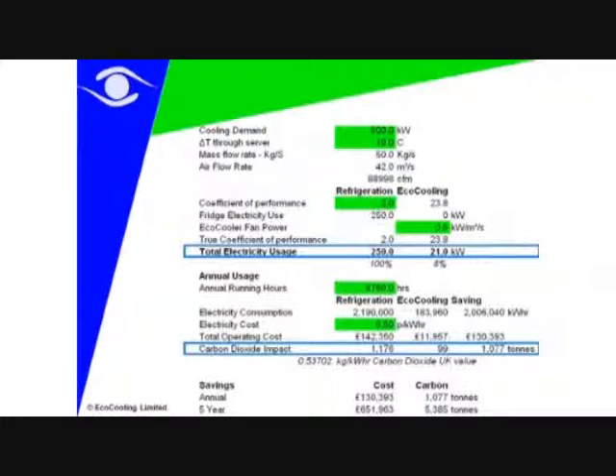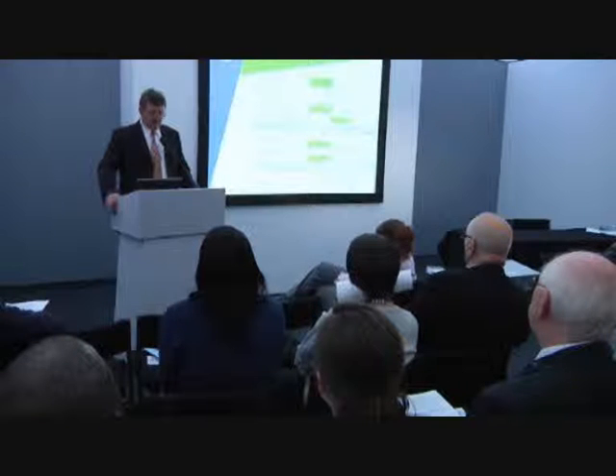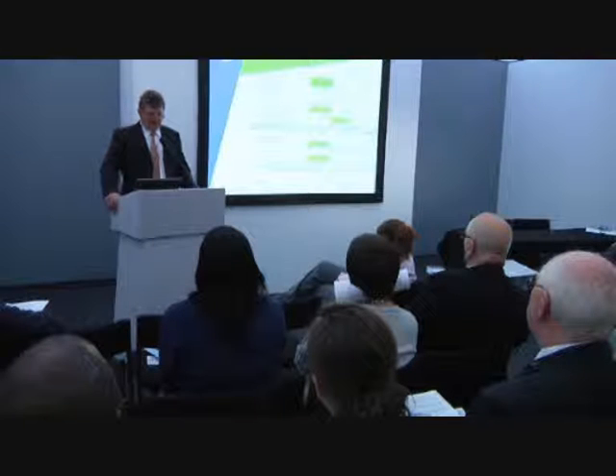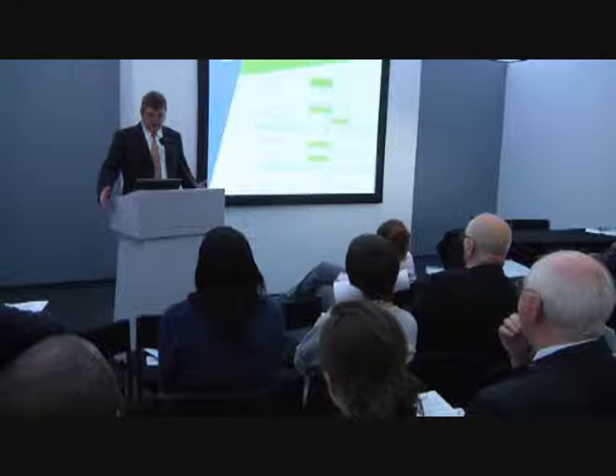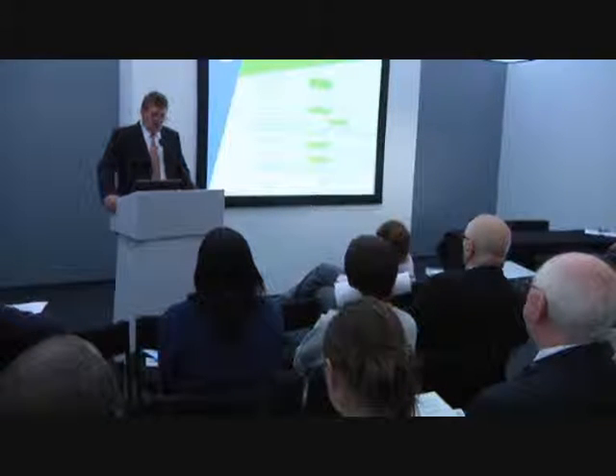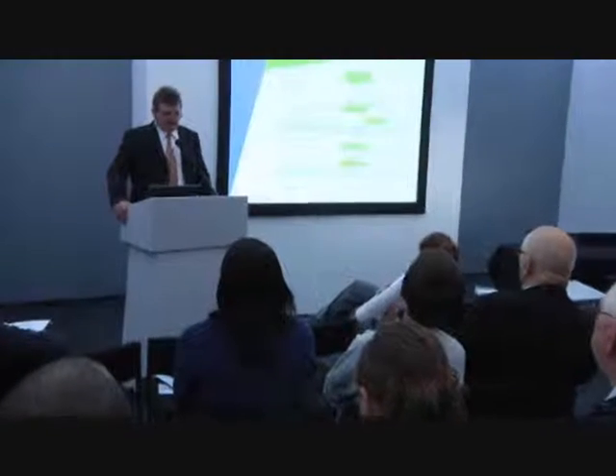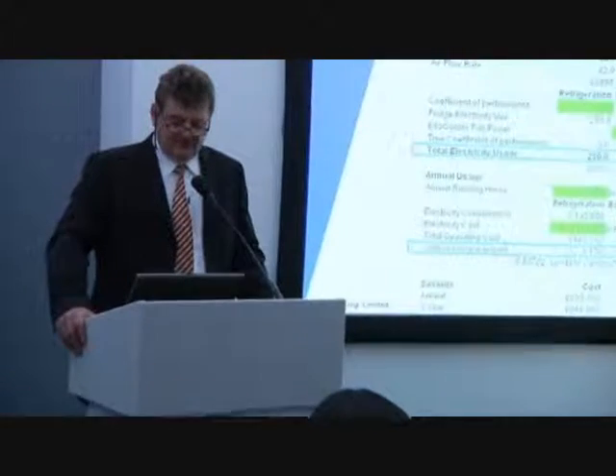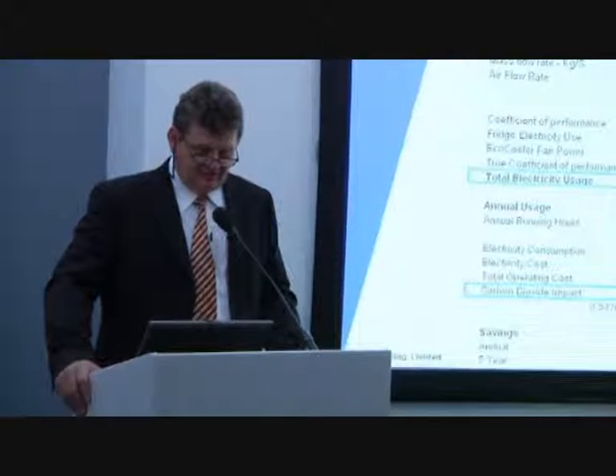The next stage of that spreadsheet, you will see there's a comparative cost, two columns between refrigeration and an eco-cooling CREC system. The coefficient of performance of refrigeration in a PUE 1.6 data center will be about 2. That means for the 500 kilowatts of IT load, we will be putting 250 kilowatts of energy continuously into the cooling system. The equivalent capacity of cooling delivered by an eco-cooling CREC system would only require 21 kilowatts of electricity. So you'd see 92% less energy put into that system. A very considerable difference. Now down to the finances of this.